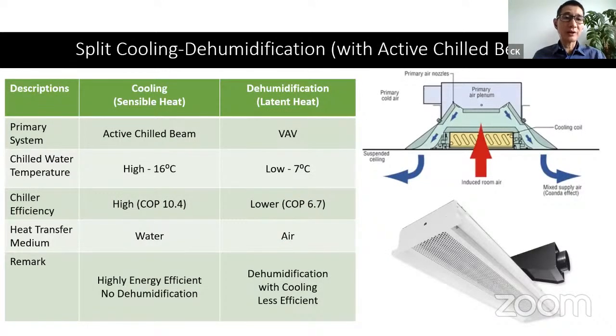Let me talk a little bit about the active chilled beam. The active chilled beam allows us to split the cooling and dehumidification of the air conditioning system, so we have two separate systems. One does the primary cooling, which is the sensible heat, using the chilled beam. We have a high chilled water temperature, which allows us to have a separate chiller supplying the chilled beam. And because of the high temperature, we get a very high COP of at least 10, as you can see here. The heat transfer medium is water.